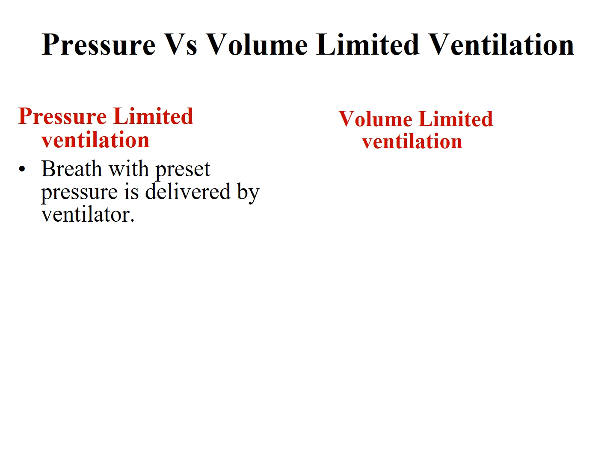So the machine triggers, in time trigger the breath is initiated, and how much ventilation is going to occur is limited either by the amount of pressure that is reached by the ventilator or the volume of breath that is going in. So in pressure limited, we have a preset pressure which is delivered by the ventilator. Beyond that, whatever happens with the tidal volume, the machine is not going to deliver more. So here the tidal volume would vary depending upon the compliance of the lungs, the resistance of the airways, and the size of the tube.